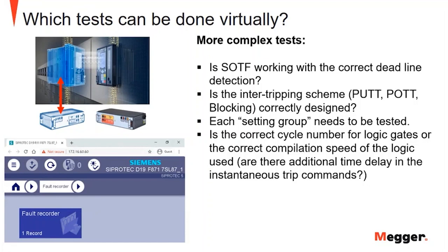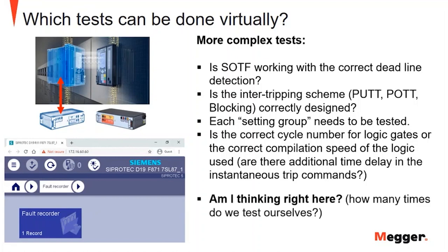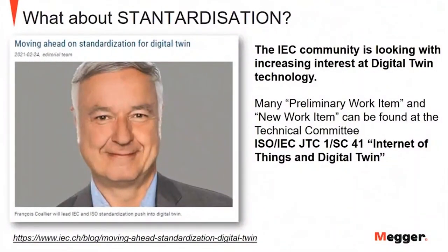For this you need a disturbance recorder, because you want to verify that you are not introducing unwanted time delays into the instantaneous trip logics. And also, by the way, you can do many tests that are not reported, and these tests you do only because you want to verify that you are thinking right, or that you have been thinking right. So, when we talk about new technology, new ideas, it's always very important to verify what the standardization does.